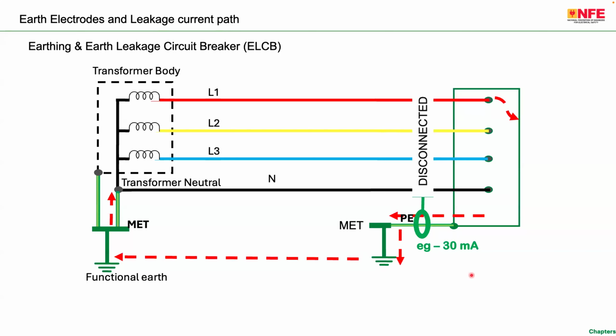Now, the problem of an ELCB is, imagine you have a wrong connection. Instead of measuring the leakage current in one PE conductor, if you have one more connection, the ELCB will malfunction. It won't function properly and won't do its desired job. Similarly, the next biggest subject you should always consider is that ELCBs require a connection to the earth electrode. If there is no earth electrode, both at the consumer premise as well as at the source, for the fault current to flow, ELCBs won't work because there is no current flow through the PE conductor.